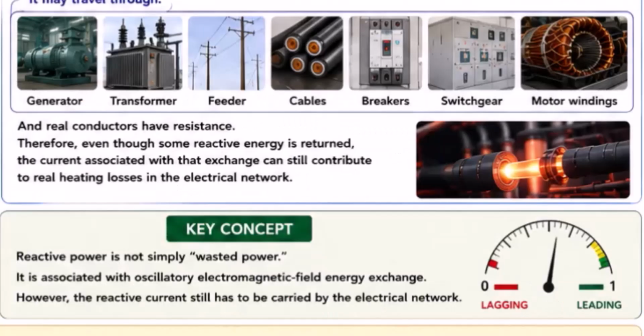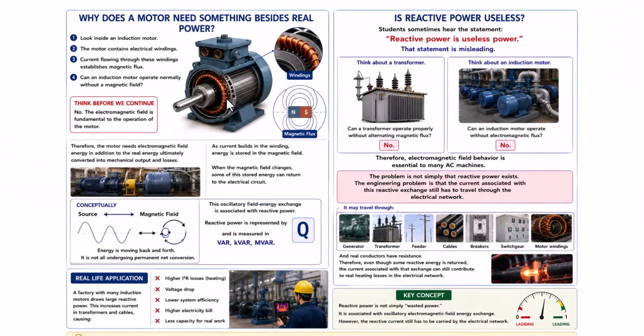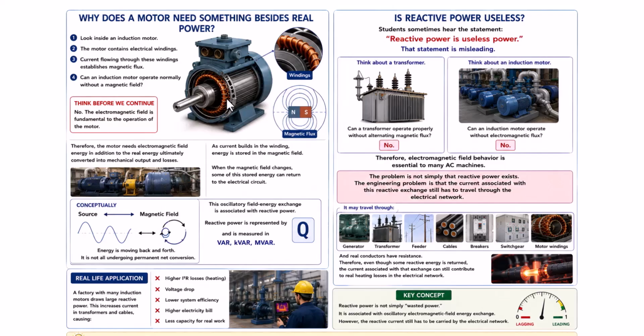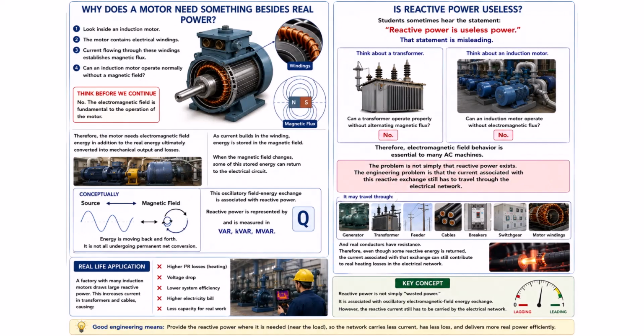It may travel through the generator, transformer, feeder, cables, breakers, switchgear and motor windings, and real conductors have resistance. Therefore, even though some reactive energy is returned, the current associated with that exchange can still contribute to real heating losses in the electrical network. The key concept is that reactive power is not simply wasted power, it is associated with oscillatory electromagnetic field energy exchange. However, the reactive current still has to be carried by the electrical network.